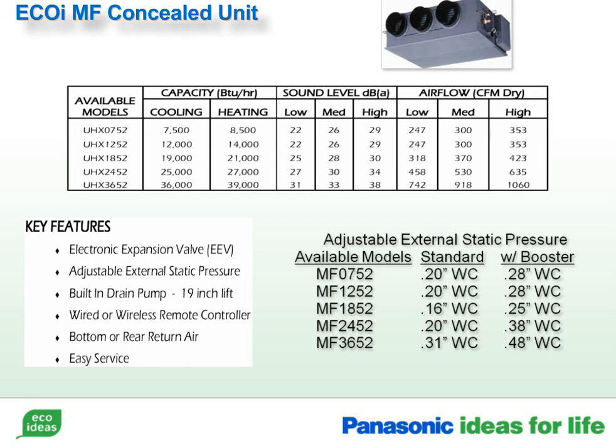The MF concealed units have 2, 3, or 4, 8-inch duct collars. These collars may be removed for use with a plenum that is field fabricated and attached. The amount of duct work you can attach is limited by the static pressure ratings for the model being installed. You must stay within these limitations to maintain proper airflow. The external static pressure is adjustable by using the included booster harness. These units are typically suspended with threaded rod.